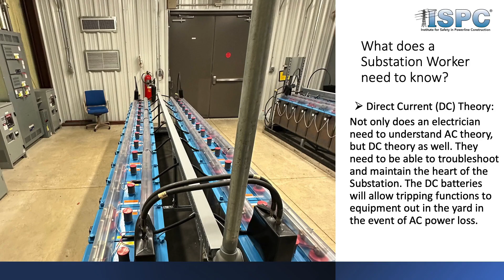We need to understand electrical theory, both AC and DC, and be able to interpret diagrams and prints that correspond with the actual equipment in our substations. We also deal with switchgear—a whole different animal than open air equipment out in a yard. Protective relaying too—a lot of substation electricians get into relaying, so we need to understand not only the power side but the relay side. Again, a very vast array of equipment and systems these people need to be competent on.